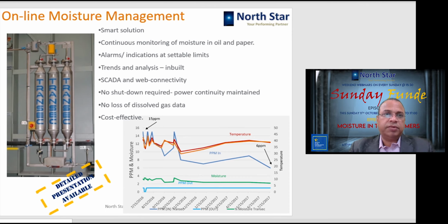As I said, we talked about online monitoring and moisture management just 2 slides before. The TRANSEC system is available, which works on the molecular sieve principle, and it has many smart solutions built into it, including continuous monitoring of moisture in oil as well as in paper. So you can know by this how much percentage moisture is there in the paper. Then it gives different kinds of alarms, indications, and settable limits. All these trends are possible for the ppm.